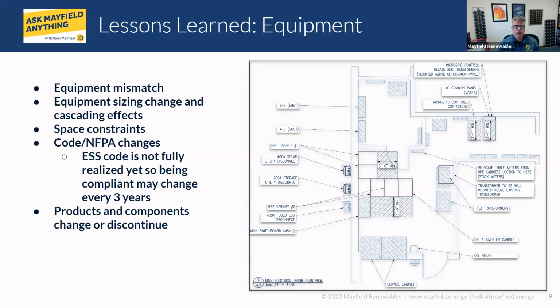We're showing a plan view of an electrical room where some equipment was going. One of the things that really has to be considered is getting conversations going with the manufacturers early and often, because size change, physical size change, current size change, power change in the output of the array or the inverter, things like that can have big impacts.